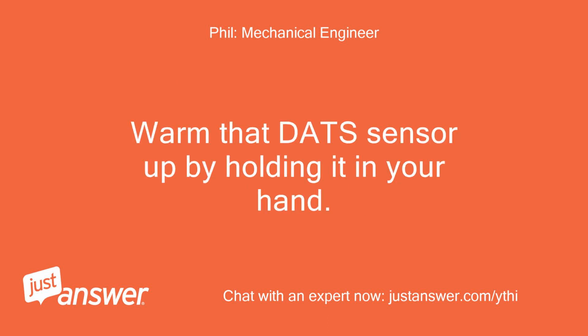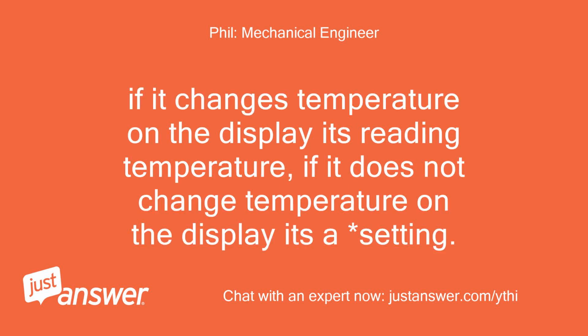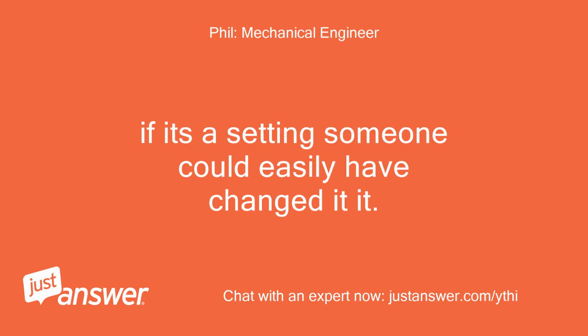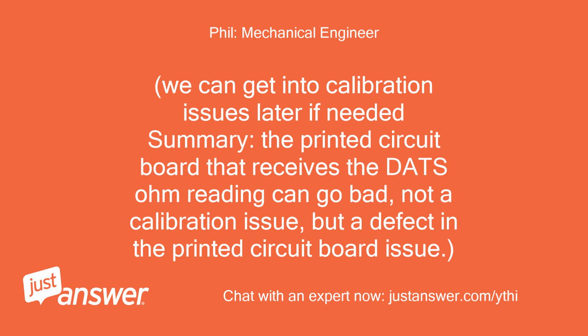Warm the DATS sensor up by holding it in your hand. If it changes temperature on the display, it's reading temperature. If it does not change temperature on the display, it's a setting. You mentioned earlier that it used to read 56F, I believe. If it's a setting, someone could easily have changed it. We can get into calibration issues later if needed.